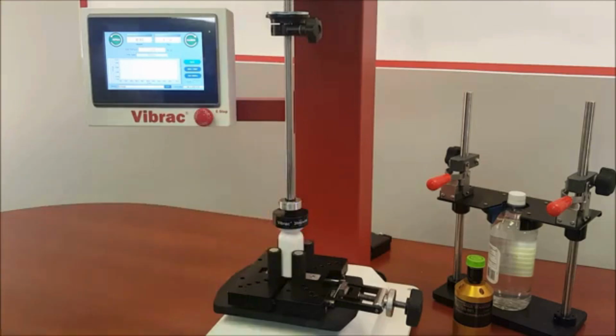Press the Open button, and the Cap Inspector will apply opening torque to the cap until it begins to move. Then it will stop and reapply the cap to the preset torque entered when creating the profile. Since the movement of the cap is at the breakaway point, the seal is not compromised, making it a non-destructive test. The data gathered will be displayed on the touch panel screen after the test.